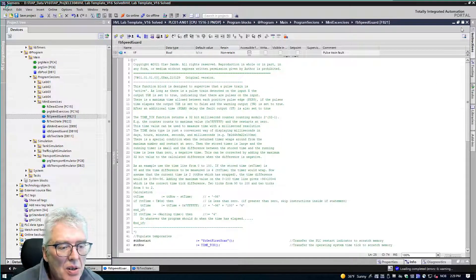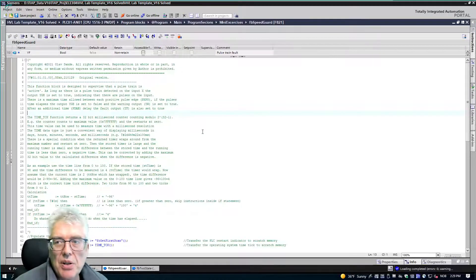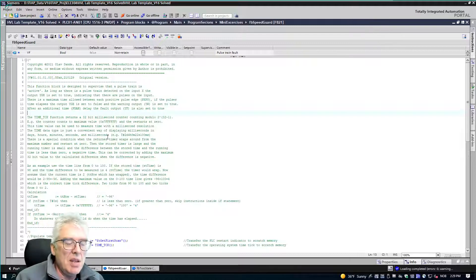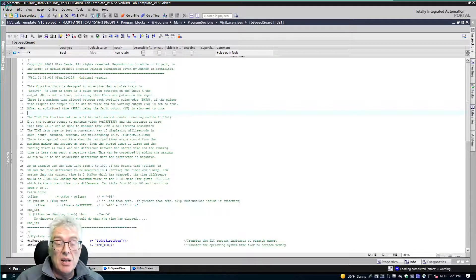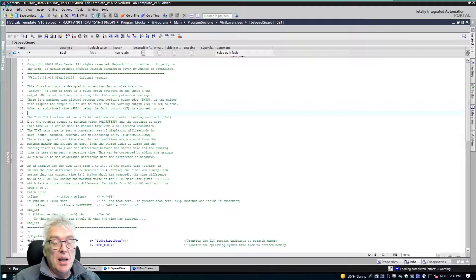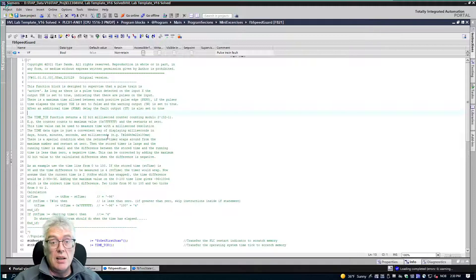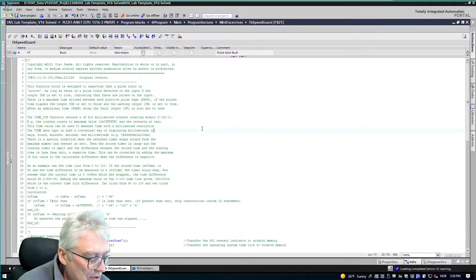That was the declaration — it's the code that's interesting. For timing, we use something called a time tick from the operating system. The OS provides a millisecond counter that counts modulo 2 to the power of 32 minus 1, which is roughly 2 billion milliseconds — about 24 days — then restarts at zero. In process or factory automation, we are not going to measure anywhere near 24 days, so this is a very convenient timing source.